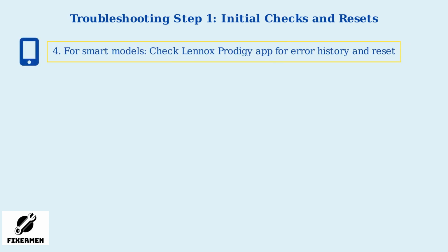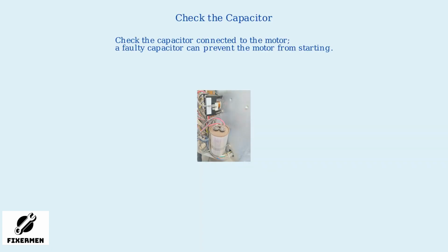For smart models, check the Lennox Prodigy app for error history and try a system reset through the app. A simple reset can sometimes resolve the issue, especially after a power surge. If the reset doesn't work, visually inspect the fan motor for any signs of damage or obstruction. Look closely at the motor housing, blades, and wiring connections for visible wear, cracks, or blockages that could prevent proper operation. Next, check the capacitor connected to the motor. A faulty capacitor can prevent the motor from starting by failing to provide the initial electrical boost needed for the motor to begin rotation. Inspect for bulging, leaking, or discolored casing.